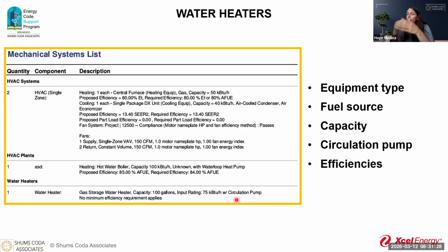That's why you see a lot of the systems utilizing circulation pumps, because that plumbing where the takeoff is to go to the fixture, the entire piping system there is considered to be your heating source. So the 6 inches that you get comes off of that line. So knowing that you have a circulation pump included is important, and it gives us that information there.